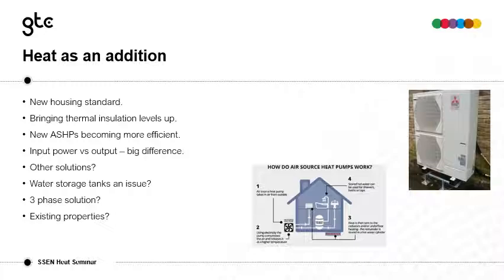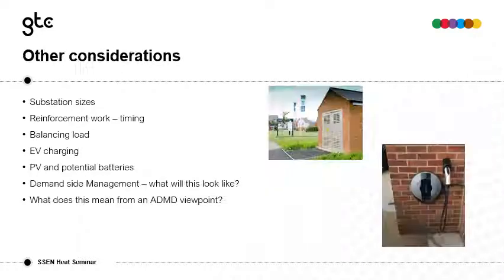...then it'll make it more the case that the older properties that are converting to air source heat pumps, because those pumps will have to be bigger since the thermal efficiency of the properties aren't going to be as big, there's going to be a significant increase in load in those properties. Air source heat pumps there will be more in the size of 10 to 12 kilowatts input, as opposed to the brand new houses, which are somewhere in the region of 4 to 6 kilowatts. So that's one of the areas to consider in terms of sizing of the air source heat pumps.